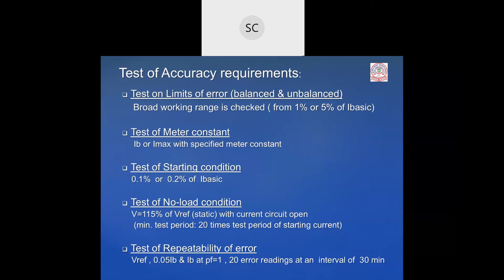Voltage variation. In case of fluctuations in the voltage, will the meter read the correct value? Will it record it? That means with variation for the same load, for example a 10 HP motor running, the voltage is varying within tolerance limits only. It may vary plus or minus 10% or 20%. In all the cases, we have to verify. Here I have shown V plus or minus 10% and plus or minus 20%. That means 240 plus 24, I have to verify, and 240 minus 24, I have to maintain.